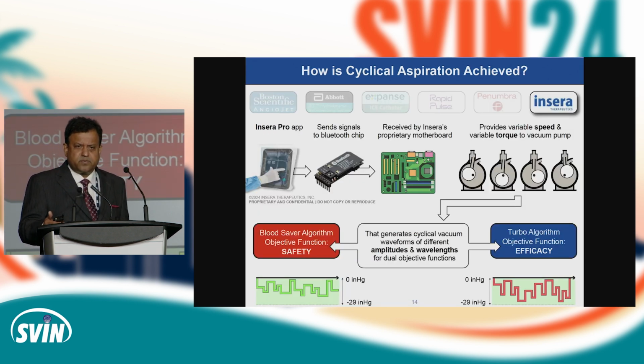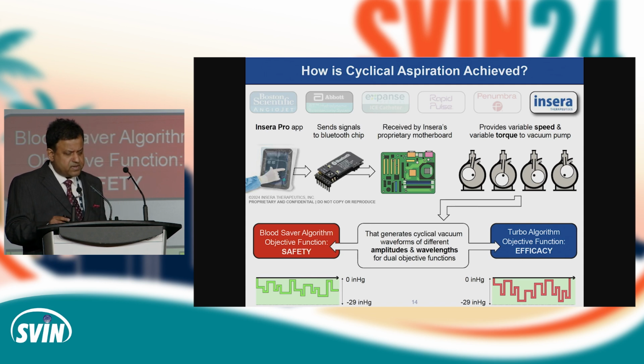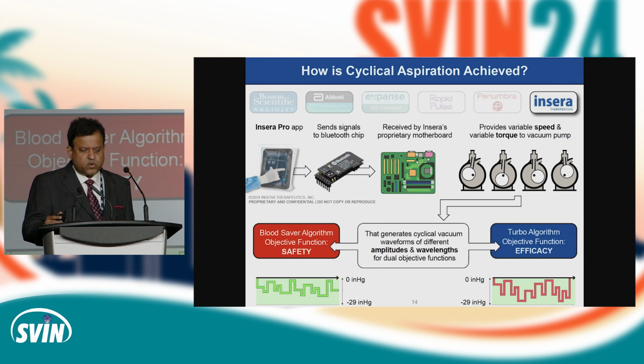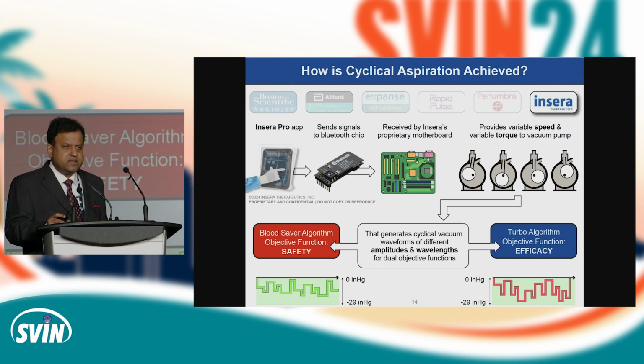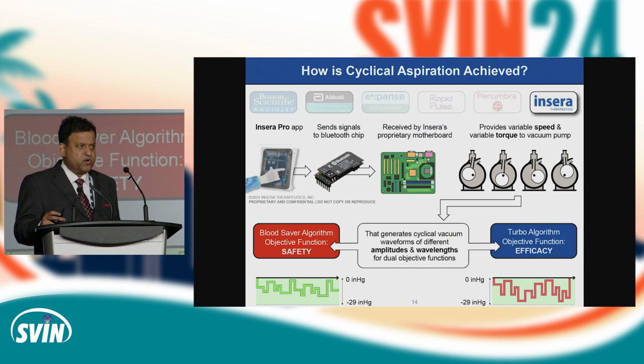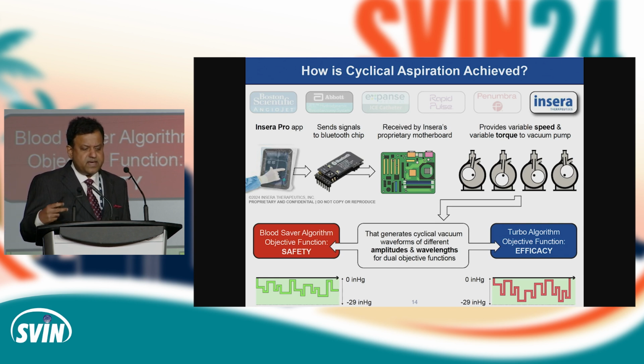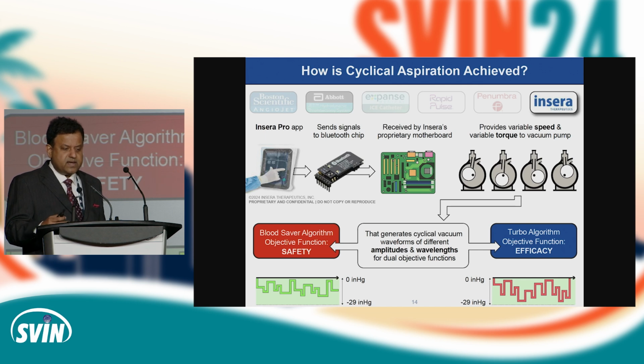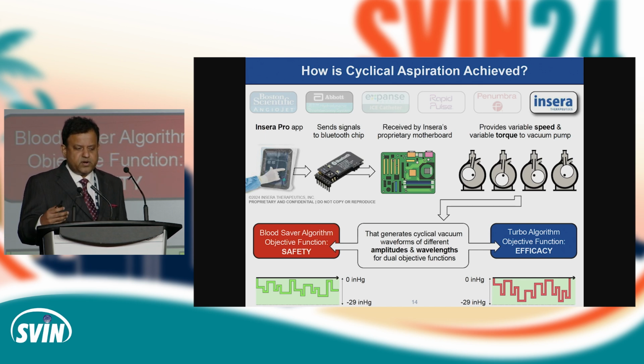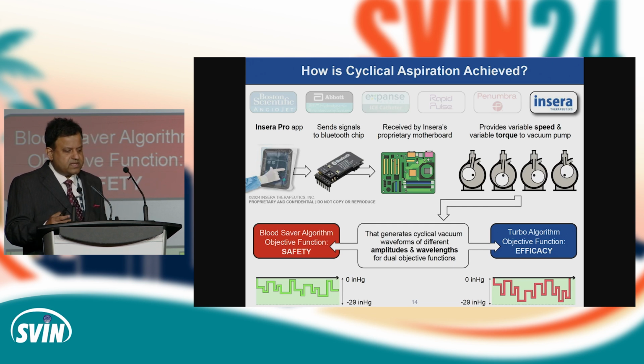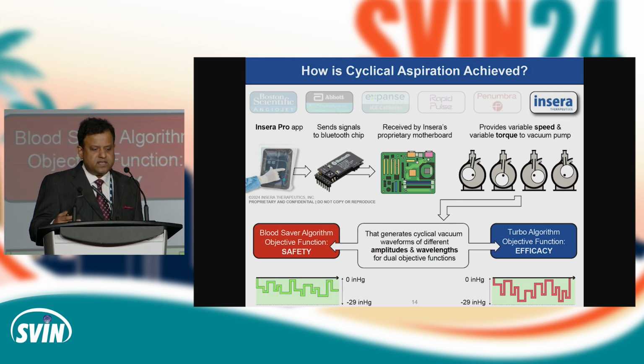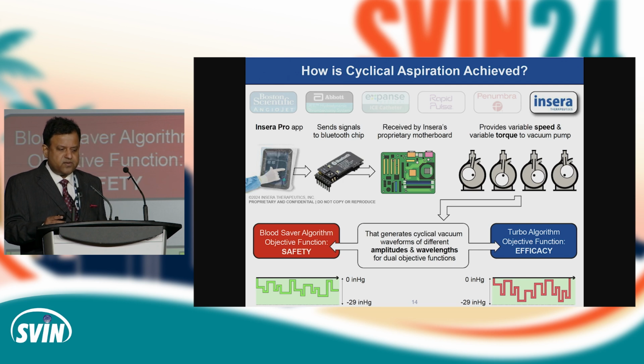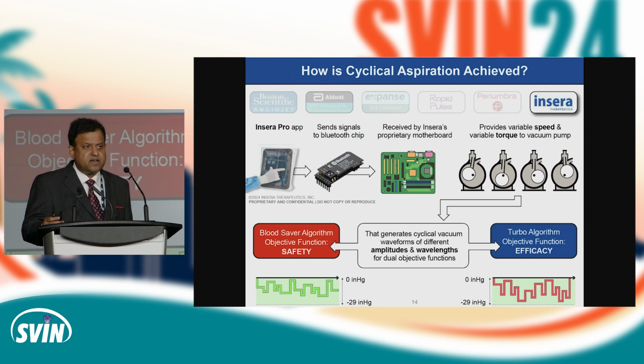Now, how is cyclical aspiration achieved? This is an example with the Insera system. You've got a tablet that can connect via Bluetooth to a chip inside the vacuum system. There is a motherboard on the inside that makes an impact on the speed as well as torque of the vacuum pump. By doing this, it's able to generate these cyclical algorithms, one which is a blood saver algorithm whose objective function is focused more on safety, so there's less blood loss, and the second, a turbo algorithm whose objective focus is more on efficacy for adherent clots.